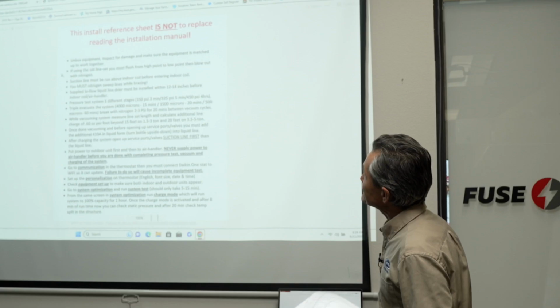I already mentioned that Daikin allows you to use old line sets, existing ones. In most cases, we replace, right, or install a new one. So this is a good benefit, but at the same time, definitely, it should be nitrogen purged. You know what nitrogen does, right? We use dry nitrogen. Dry nitrogen basically sucks out all the moisture or whatever might have been inside of that old line set. So that's why it definitely needs to be used.